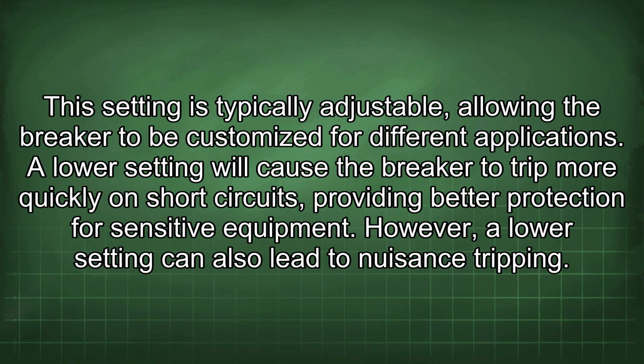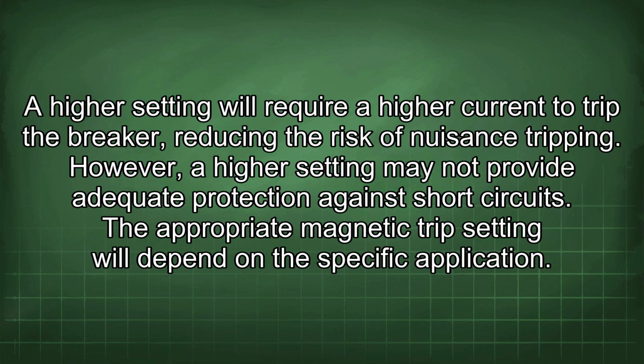A lower setting will cause the breaker to trip more quickly on short circuits, providing better protection for sensitive equipment. However, a lower setting can also lead to nuisance tripping. A higher setting will require a higher current to trip the breaker, reducing the risk of nuisance tripping. However, a higher setting may not provide adequate protection against short circuits.